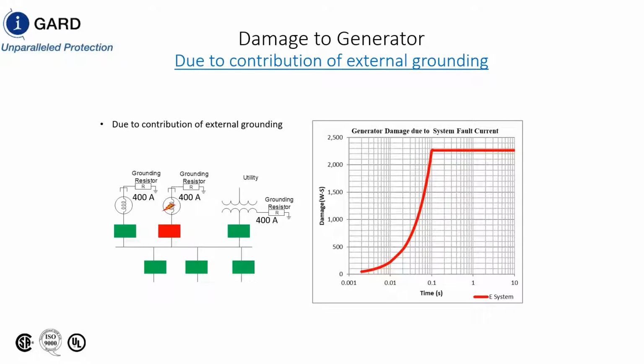So the contribution of the fault current due to this resistor and this resistor of 800 amps is 2,263 watt-seconds of damage in that fault inside the stator fault winding. If you had 4 generators or 4 sources at 400 amps, you'd have 1,600 amps. Or if each source had an 800 amp ground resistor, you would have 6,400 watt-seconds of damage. And you could see here that that fault is going to stop contributing to the stator fault winding after 100 milliseconds or 6 cycles.